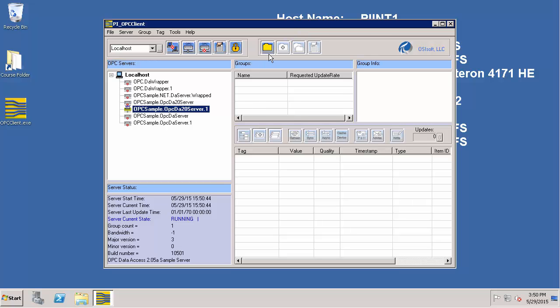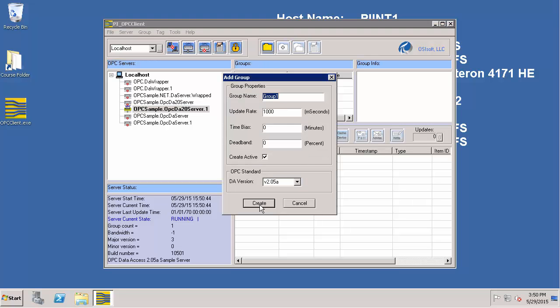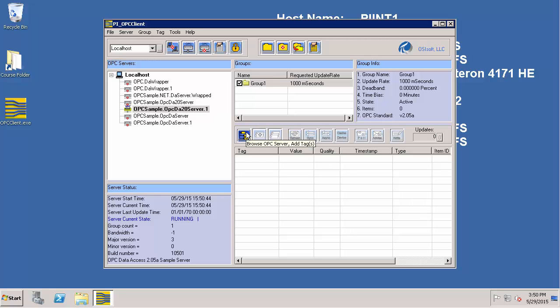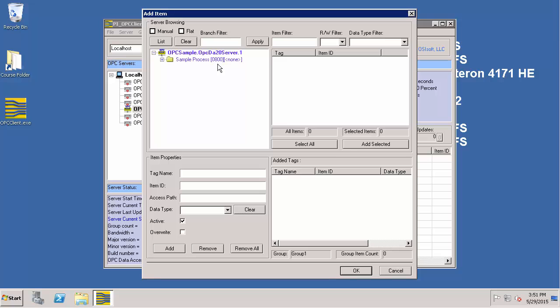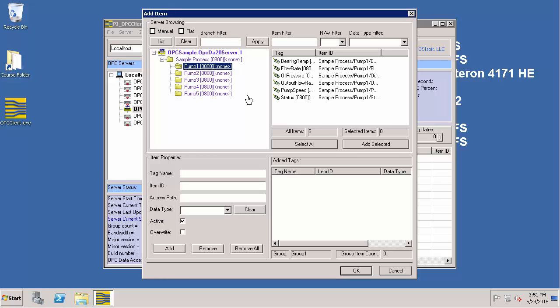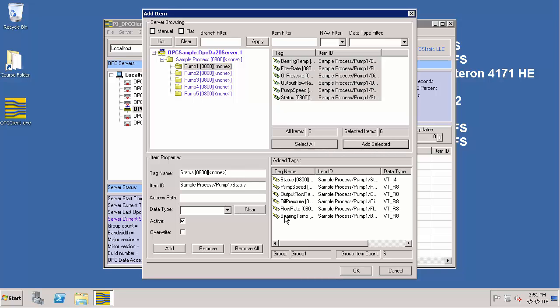Namely OPC Sample.OPCDA20Server.1. Now let's click on this button to add a group, accept the defaults and click Create. Now let's browse through the OPC server by clicking on this button. Double-click the OPC server and expand the tree. Let's select Pump 1, select all and say Add Selected. If you click on BearingTemp, this is the item ID we are interested in. Note this should be exactly configured the same way on the instrument tag attribute for the PI Point — this is case sensitive.